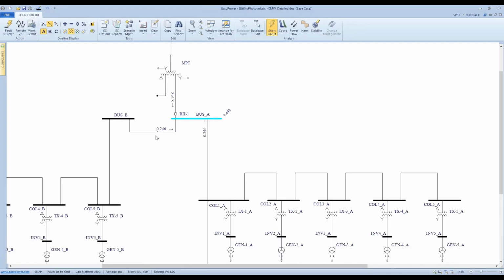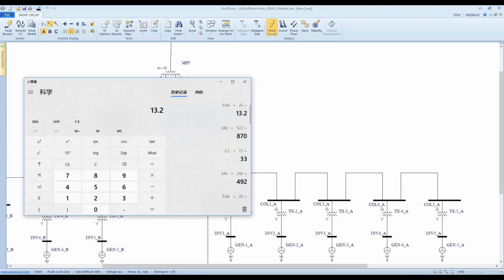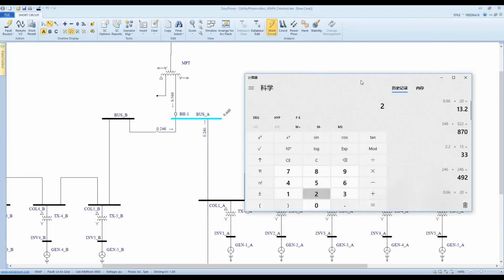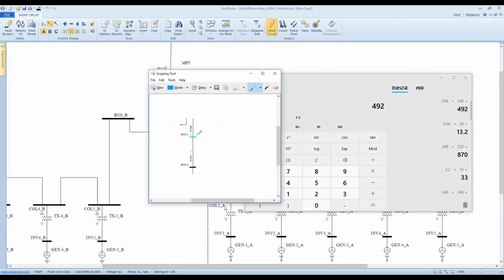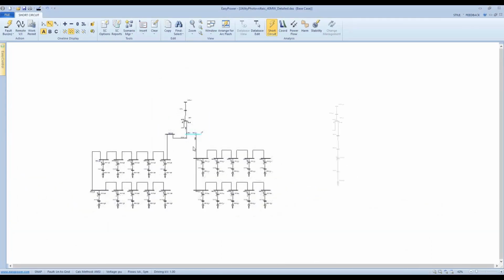What we got? We got 246 and 246. So if you add them up, 246 plus 246, that's exactly 492 ampere. So the model gives you exactly the same amount of fault current contribution between the one-line model and the lumped model, which is satisfactory.